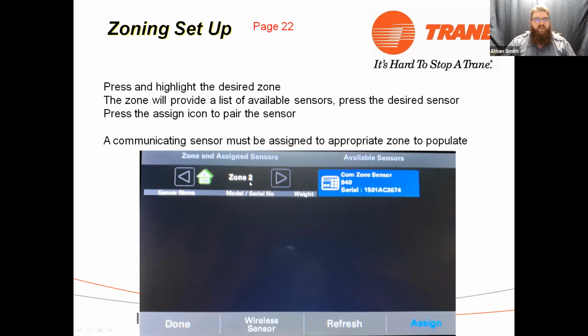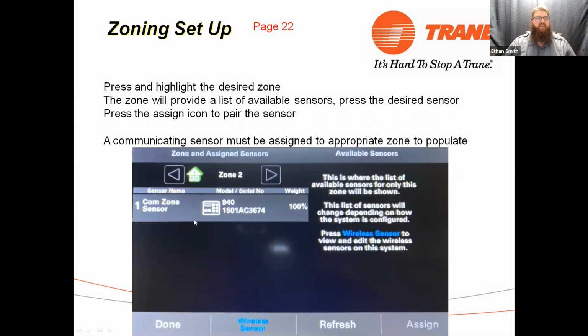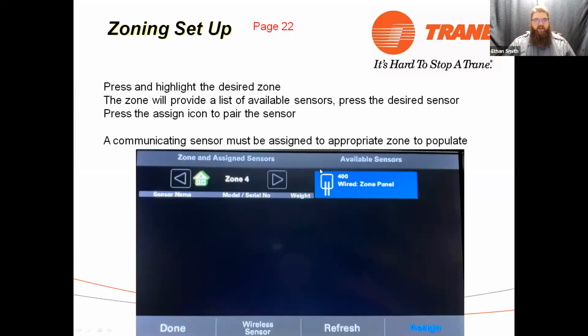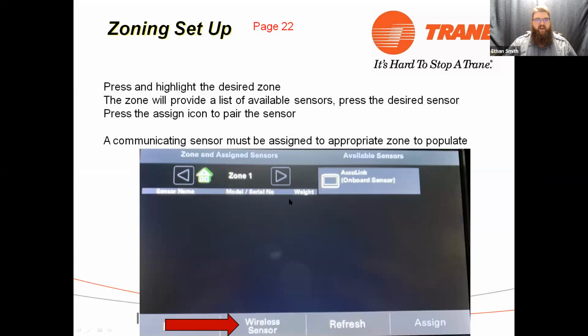So this is zone 2, and you'll see we have an available 940 for this zone. So this 940 got addressed. We used to have to address those things to zone 2. So we can click on that zone sensor and hit assign, and it will assign that zone sensor, that 940, to zone 2. Okay. Same thing if we've got a wired zone sensor, even though it's wired into zone 4, we have to assign it as the active sensor. So we'll click on the available sensor right here. We'll hit assign, and then we've got that assigned. Zone 1 is always going to default to the 1050 or the 950.